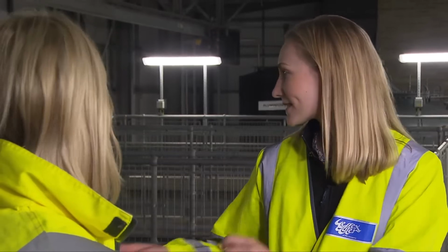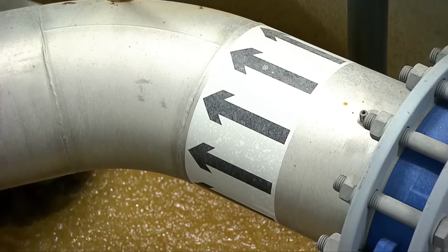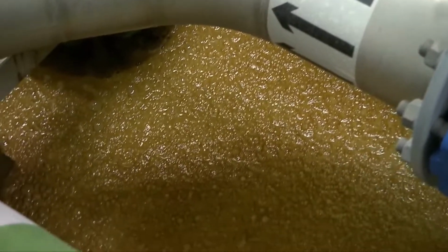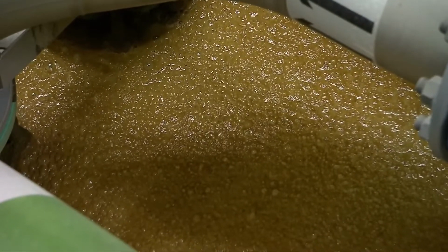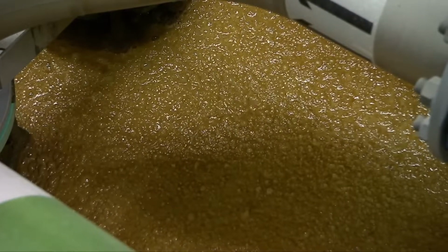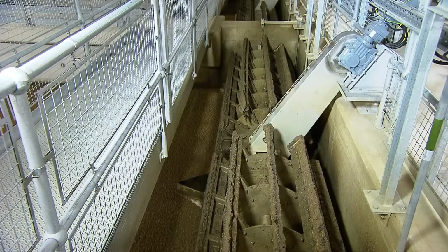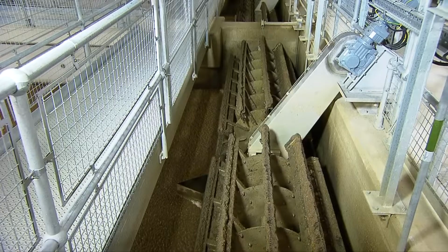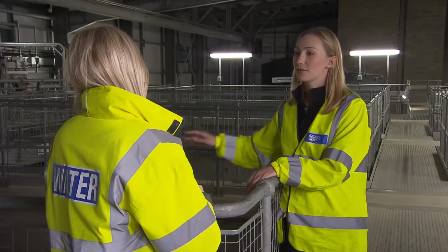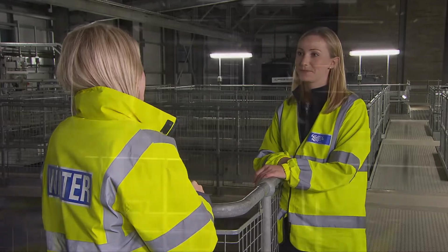What happens next? After that, the water enters the dissolved air flotation tank, known as the DAF, and here it's mixed with clean water, which is saturated with air, which when it's mixed releases tiny air bubbles which form on the flock and reduce its density, which means it floats to the surface of the tank and forms a sludge blanket. This is scraped off the top of the water periodically by a mechanical arm, and the clean water flows off underneath the sludge blanket and onto the next stage of the treatment process.